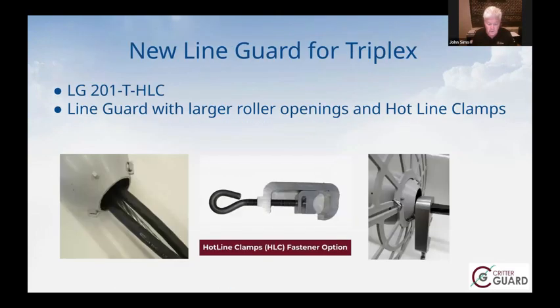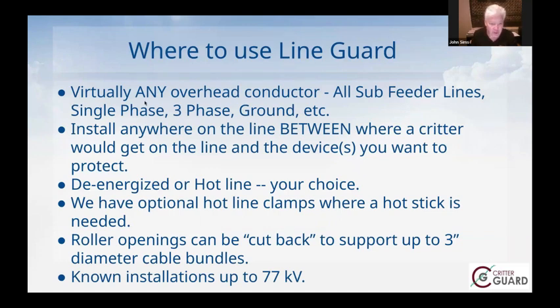Okay, moving on. More information about where you can use line guard. It's basically on any overhead conductor. We don't really care if it's a 10 kV distribution line, or 11, 35, or 77. Customers have put it on transmission lines up to 77. We generally find you don't have animal mitigation issues on very high voltage transmission lines because animals just don't climb that high, so distribution lines are where we're used the most, including feeder lines to a substation, single phase service entrance, 3-phase lines, even guy wires and structural cables. It doesn't have to be a powered line; it has nothing to do with the power.